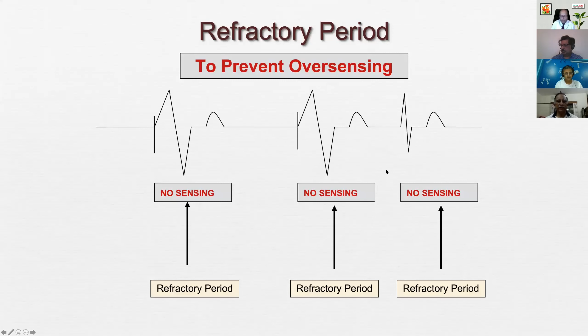There are so many other pacemaker intervals which will take a lot of time to discuss, about 45 minutes or so. So I will skip them in this talk, and we will move on to the indications and choice of pacemaker. The pacemaker battery typically is a lithium iodide battery. There are some other compounds, vanadium, etc., along with lithium, and they usually have a beginning of life value of 2.8 volts. Some pacemakers are coming with 3.2 volts also, and they contain a certain amount of battery capacity, which is utilized during the life of the pacemaker. And typically the pacemakers now last about 10 to 15 years.